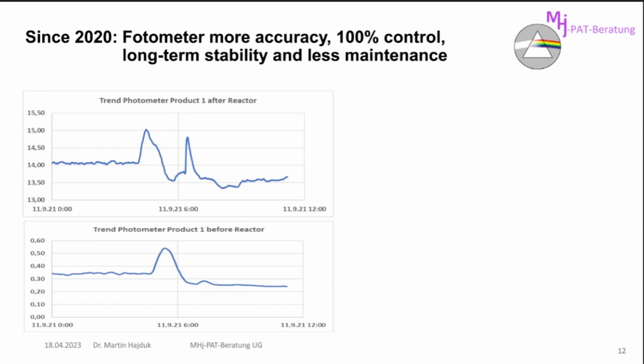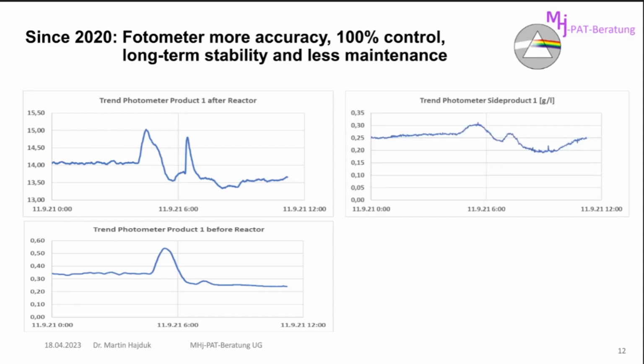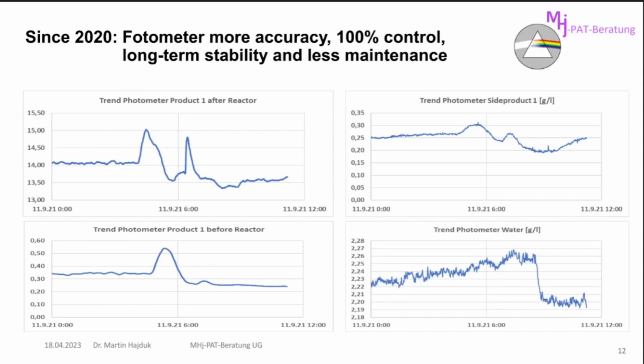And we have a look at the long-term stability. Here is the concentration of the product after the reactor. This is before. This is also over 12 hours, and you see very low noise. And here next is the water. Here, it's coming here. That's the side product. You know, before there was a lot of noise on it, and now it's really stable. And this is the water. It looks more noisy, but take care, it's from 2.18 to 2.28. So with a photometer, it's really possible to measure better than 0.05 grams per liter.